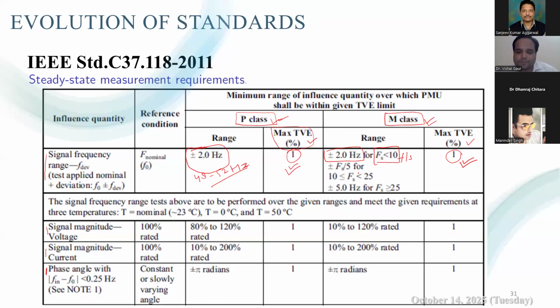If the data reporting rate is between 10 to 25 frames per second, then the range of frequency deviation is plus minus the data reporting rate divided by 5. Let's say if the data reporting rate is 20, then the frequency may deviate by plus minus 4 hertz, and the total vector error should remain within this 1% limit. In this way, they have defined the allowable total vector error limit with respect to deviations in the influence quantities. Similarly, you can observe for voltage and current.